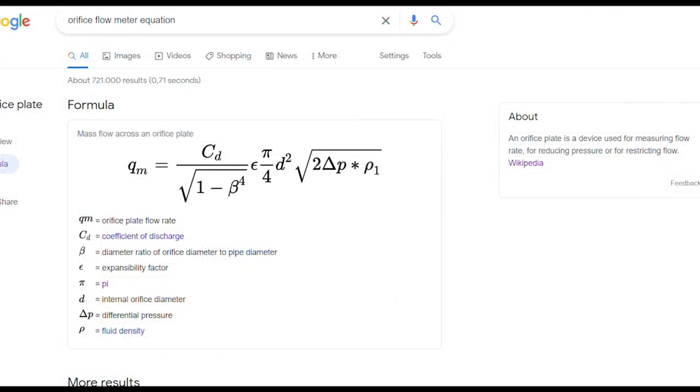Another example of where we use discharge coefficients is in the orifice equation for orifice type flow meters. Most of the equation for the mass flow rate through an orifice comes from a derivation of Bernoulli's equation similar to what we did at the beginning. Then in order to make it match experimental data, you can see it also has a coefficient of discharge in the front.